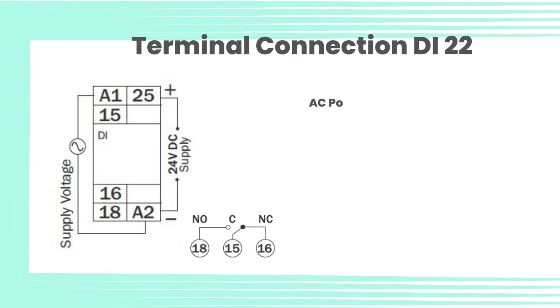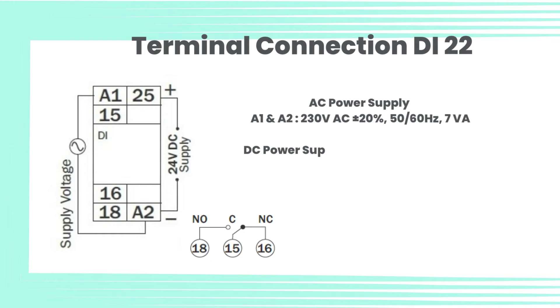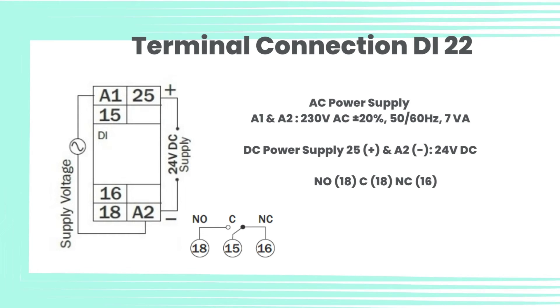Terminal connection DI22. AC power supply: A1 and A2, 230V AC ±20%, 50/60 Hz, 7VA. DC power supply: 25(+) and A2(-), 24V DC. Relay terminals: NO-18, C-15, NC-16.